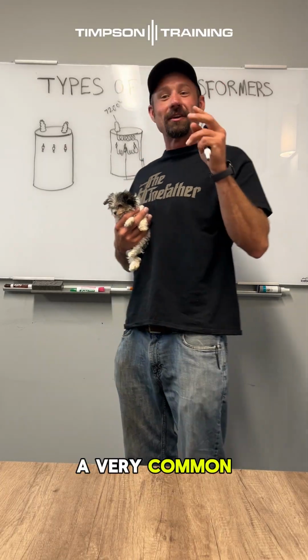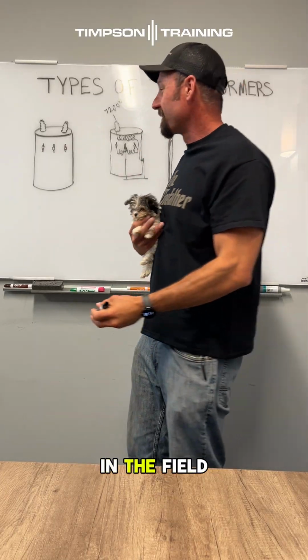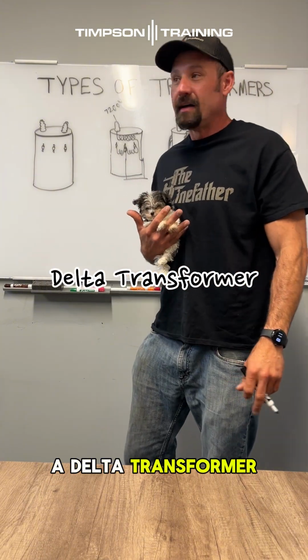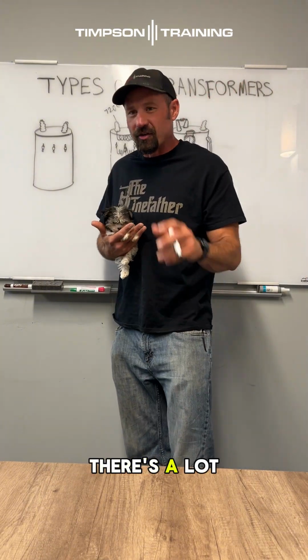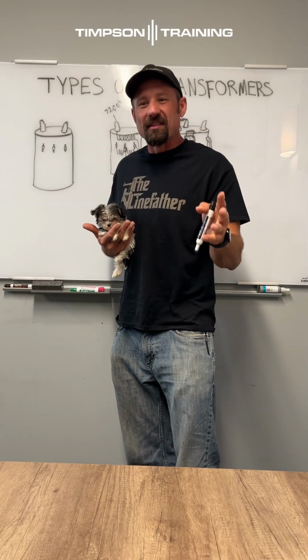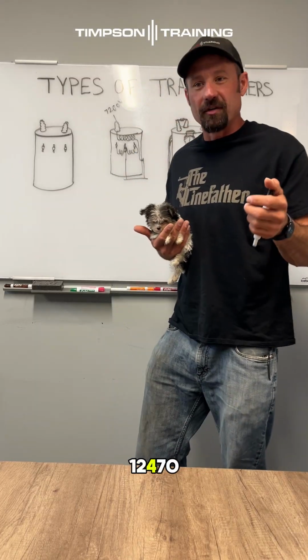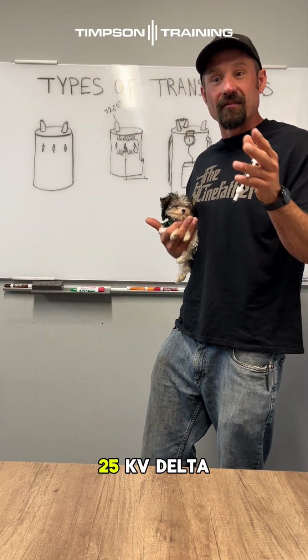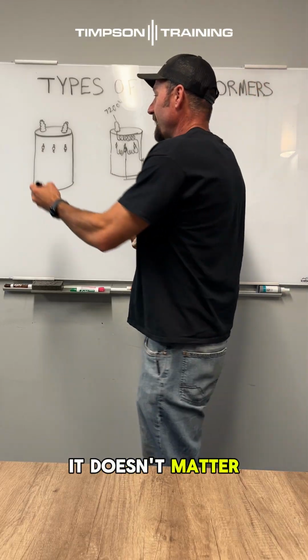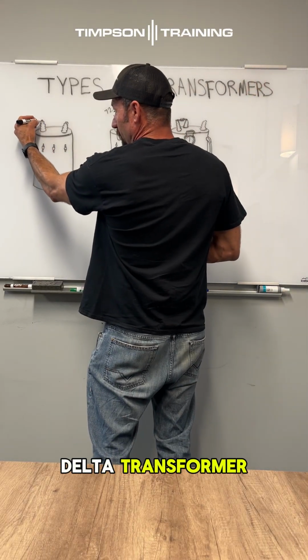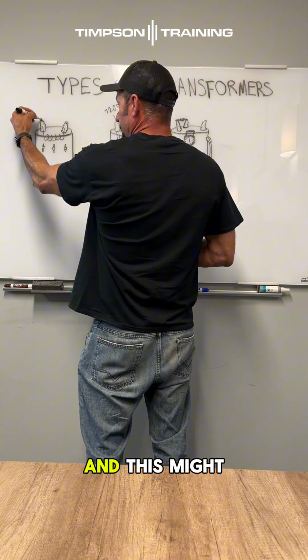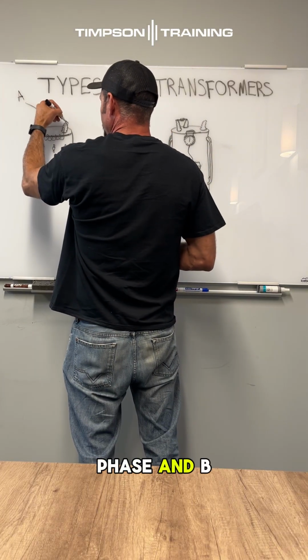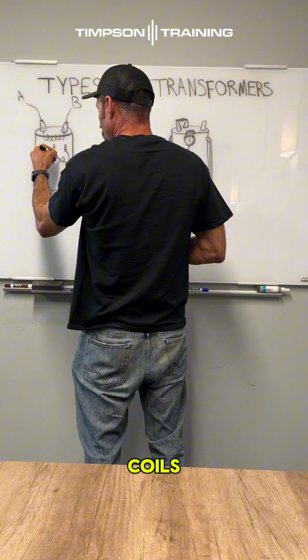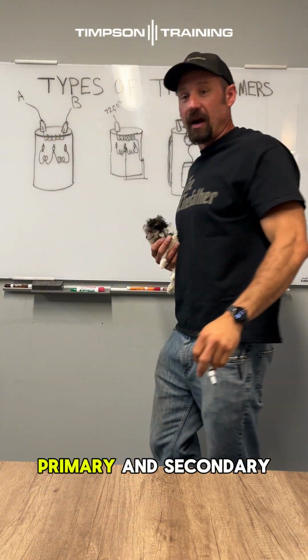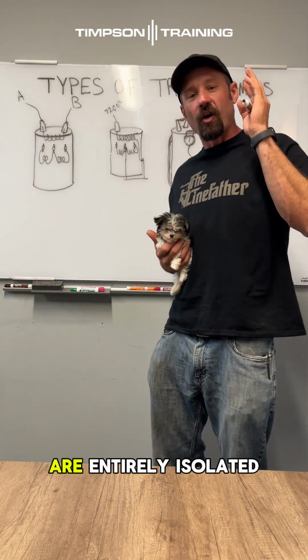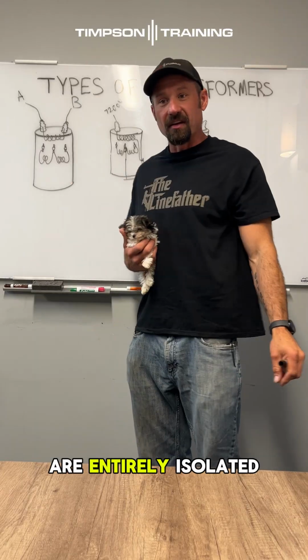A very common type of isolation transformer you're going to see in the field is a delta transformer. And I've said this the other day, you have 4160 delta, you can have 12470 delta, you can have 25 kV delta. It doesn't matter. But if we look at the delta transformer, your coil goes like this, and this might go to A phase and B phase. Then your secondary coils. Now these two primary and secondary coils are entirely isolated.